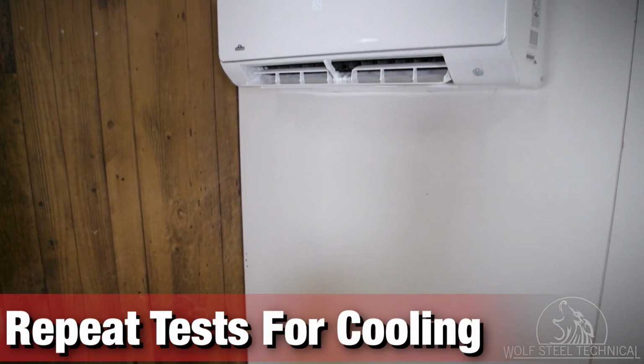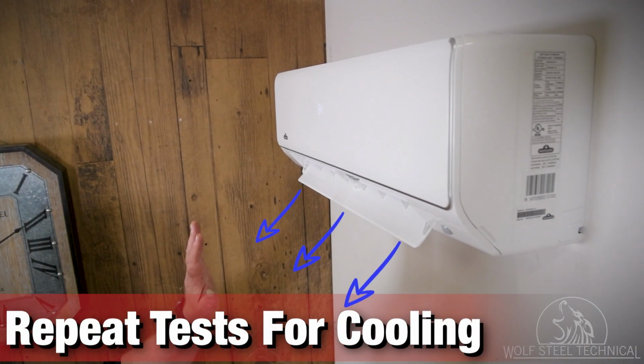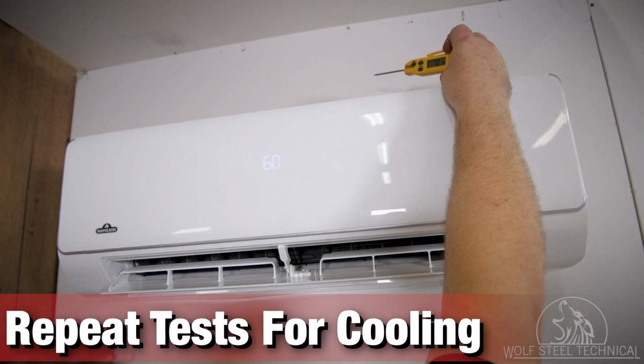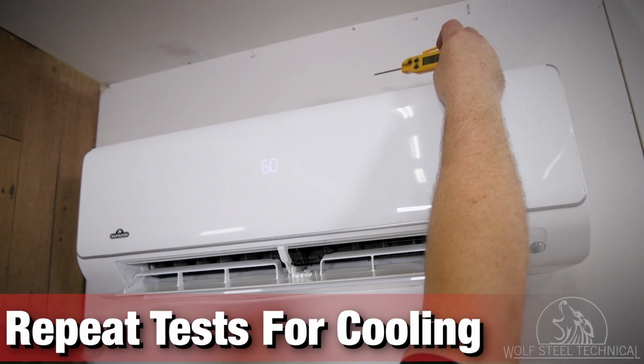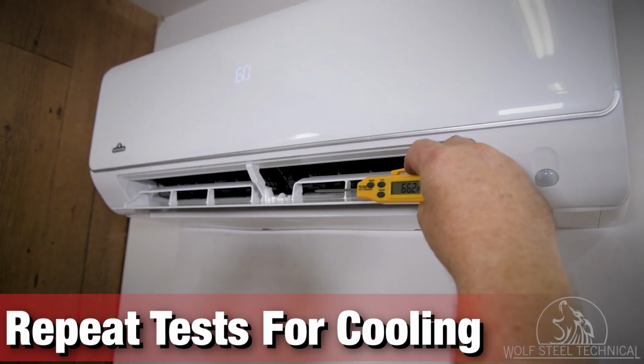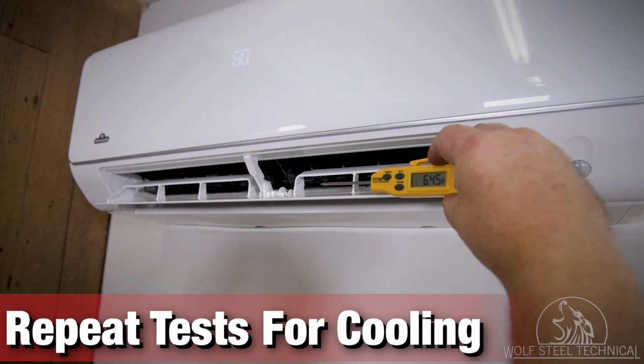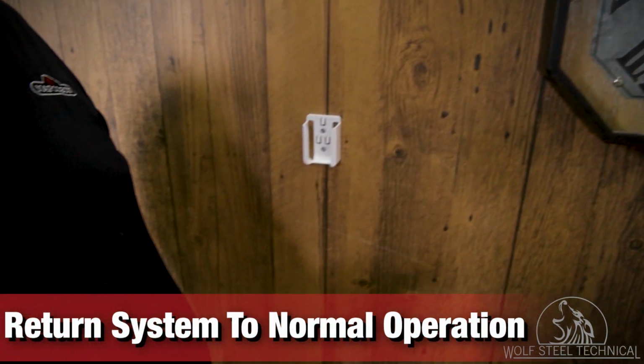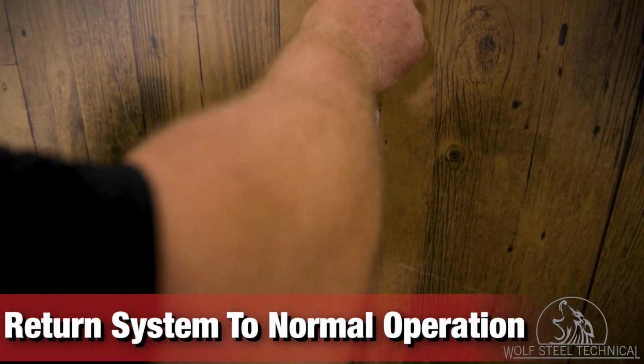Repeat the same tests for the cool setting to ensure both the heat and cool functions are operating as intended. Approximately 20 degrees Fahrenheit is a typical drop in temperature when testing the cooling function. Once the test run has been completed, the unit can be returned to normal operating temperature and left with the customer.